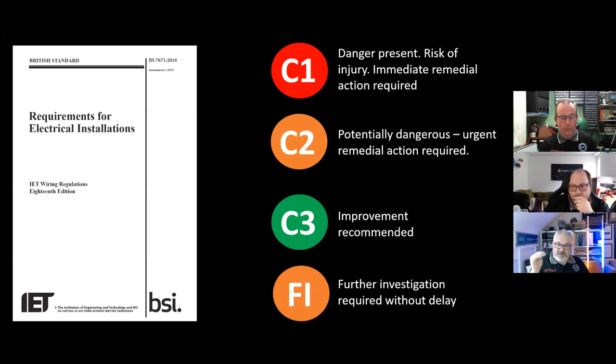And the only other use, again, of FI would be Regulation 653.2, which is covered under the extent and limitations. If the client says, I only want you to test the sockets and the earthing, that's all you're testing. But again, there's that box where you would have the limitations agreed by the client, and the client would sign that. Yeah, and so that covers FI or limitation.